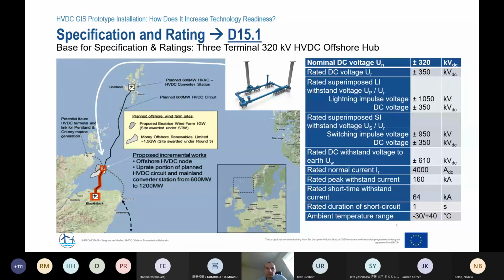So the first step is the specification and rating. In Work Package 15 in PROMOTION, how did we come up with specification and ratings for HVDC GIS? The specification was done on the example of a 3-terminal 320 kV HVDC offshore hub. The example that was used there was a connection from Shetland to Scotland. It is an HVDC link where, basically in the middle of the link, an offshore wind farm is added that should be connected to the link, and so there we should have a 3-terminal HVDC hub to connect this offshore wind. In deliverable D15.1, which I've also linked here, you can read more details.